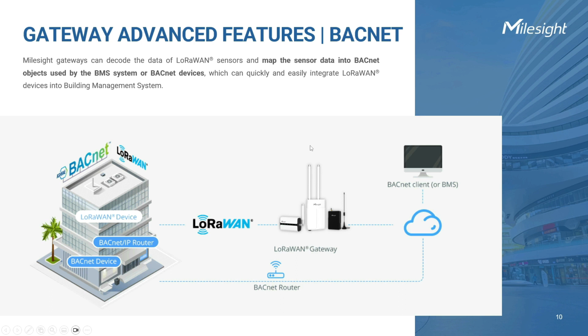Well, Milesight UG67, UG65, and UG56 gateways open up pathways to achieve that. Suppose the company would like to install the LoRaWAN-based room or desk occupancy sensors and indoor air quality sensors. Without the need for fixed hardwired infrastructure, the data generated by these sensors can be quickly fed into the legacy BACnet system using Milesight's LoRaWAN gateways that support the BACnet IP protocol.